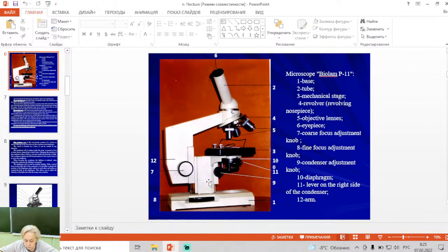See again on this microscope how to view an object under the microscope. Use the coarse focus adjustment knob to maximize the working distance. It's the distance between the stage and the objective lens. Rotate the revolver into position with the scanning power, times 8, objective lens, in the viewing position. Turn the revolver until you hear a slight click and the lens is fixed.